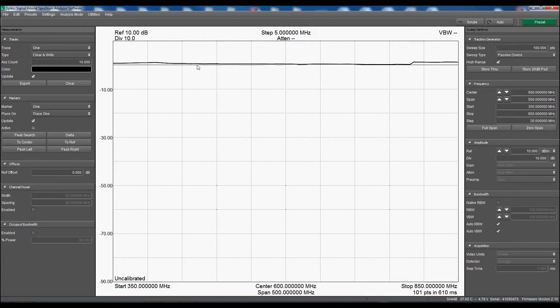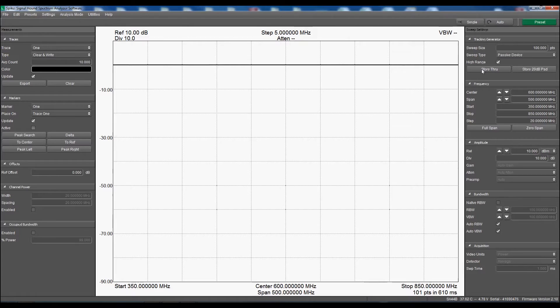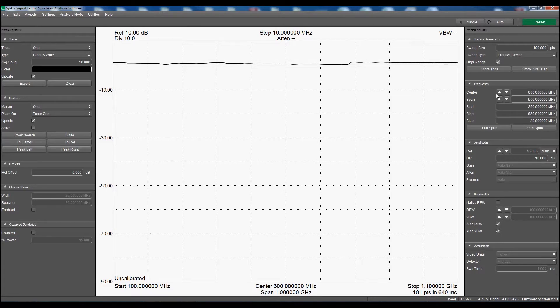Now we can see the trace is not exactly on the 0 dB line. Only rough corrections are applied at this point, so don't be surprised if it is a few dB off. Let's fix this by clicking Store Through. After a second or so, we should see a nice flat line at 0 dB. Note that if we change frequency or span, the THRU data is lost and must be re-run for accurate measurements.